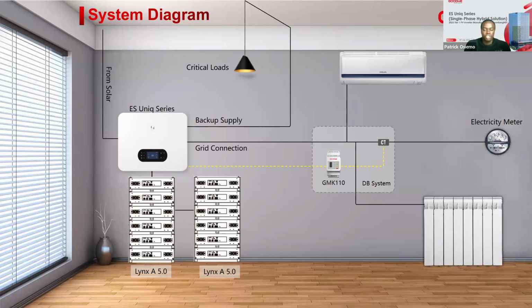If the distance is short, the CT is very much capable of achieving the export limitation and load monitoring. The CT is installed at the grid side, then we have the loads and the batteries. You can fully back up or segregate your loads in terms of criticality - put some on the on-grid port, some on the backup port, or all of it in the backup port, because we have up to double the surge supporting capability for a maximum of 10 seconds.